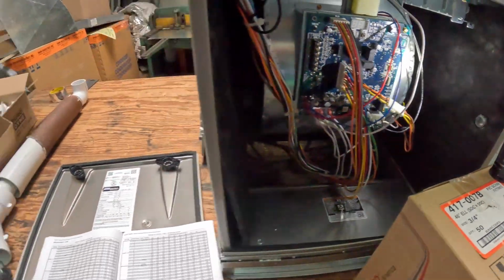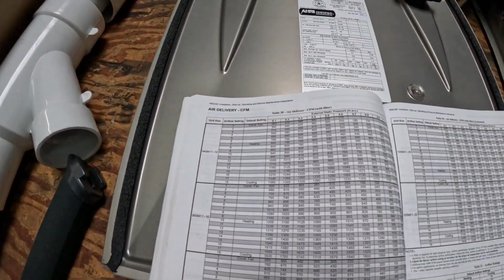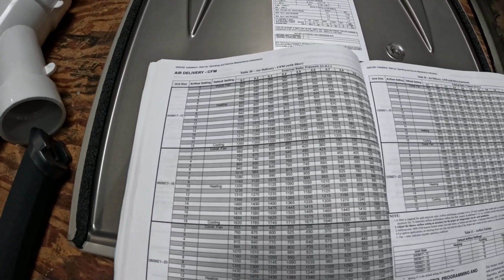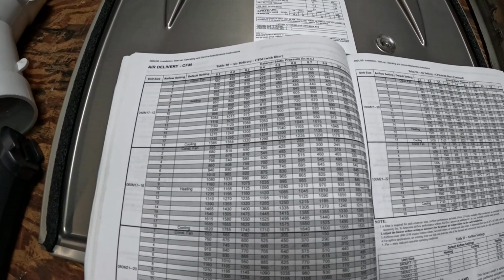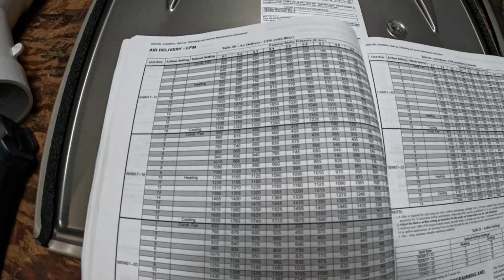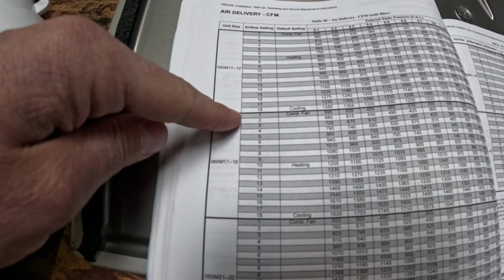Again, you are going to need to go to your book and look at the CFM chart. Decide what your static pressure is by knowing what your ductwork size is and all that. And you're going to use these numbers here as references and follow it over to your static pressure.